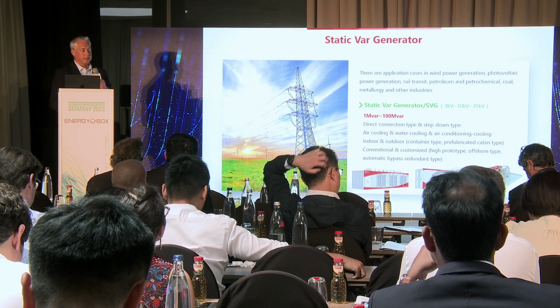The benefits of having an SVG system include increased efficiency on both the output and input of the system and devices, a reduction in cable size which reduces the cost of copper, an increase in available power, elimination of the penalty for low power factor from the electrical supply company, a saving in energy, and reduced cost of the electrical devices and equipment.